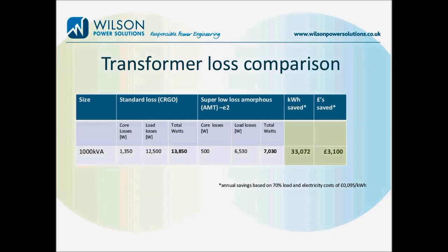But in terms of actual energy savings, the super low loss unit saves over 33,000 kilowatt hours per annum, which is over £3,100 per year, and we base that on a tariff of 9.5p per kilowatt hour. It's important at this stage just to note that there are currently no industry standards classifying super low loss transformers. So as a purchaser looking into buying a low loss or a super low loss unit, it's really important to ask for loss values, perhaps create a table and compare them with competitors out there in the marketplace.